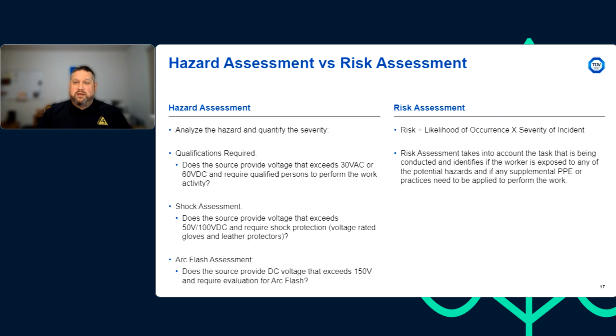Let's say we have a high energy battery sitting in the bottom of a vehicle we're going to be driving. That has a high hazard, but it's enclosed, it's insulated, and we have monitoring systems making sure everything's okay, so we're not intruding onto any energized components. Do we need to wear any additional PPE to drive that vehicle, or need any additional training? No, we do not. But as soon as we start to do maintenance on that system, where we might break that threshold and expose energized conductors, now we need training, and now we need to possibly implement PPE depending on the state of that system.